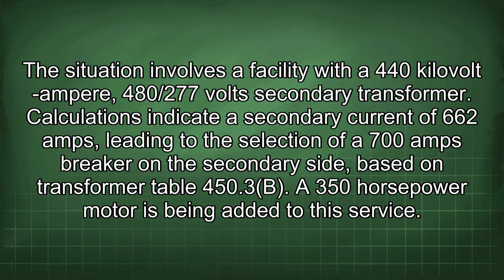The situation involves a facility with a 440 kVA, 480/277 volt secondary transformer. Calculations indicate a secondary current of 662 amps, leading to the selection of a 700 amps breaker on the secondary side, based on transformer table 450.3(b). A 350 horsepower motor is being added to this service.